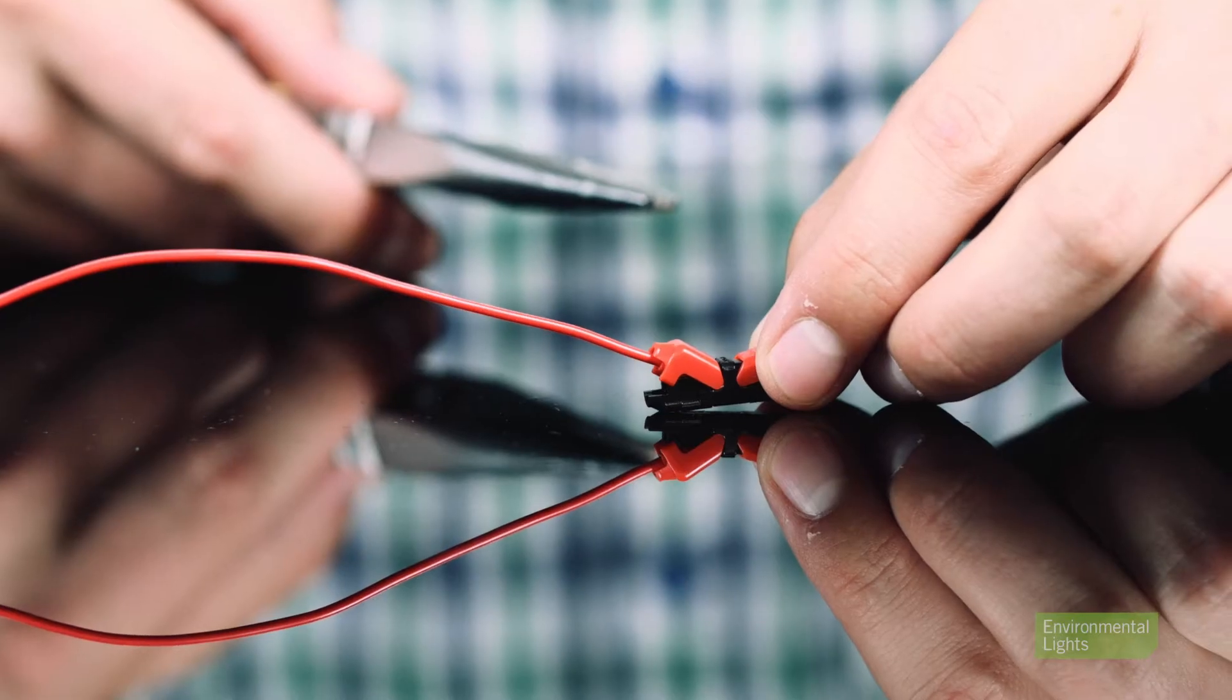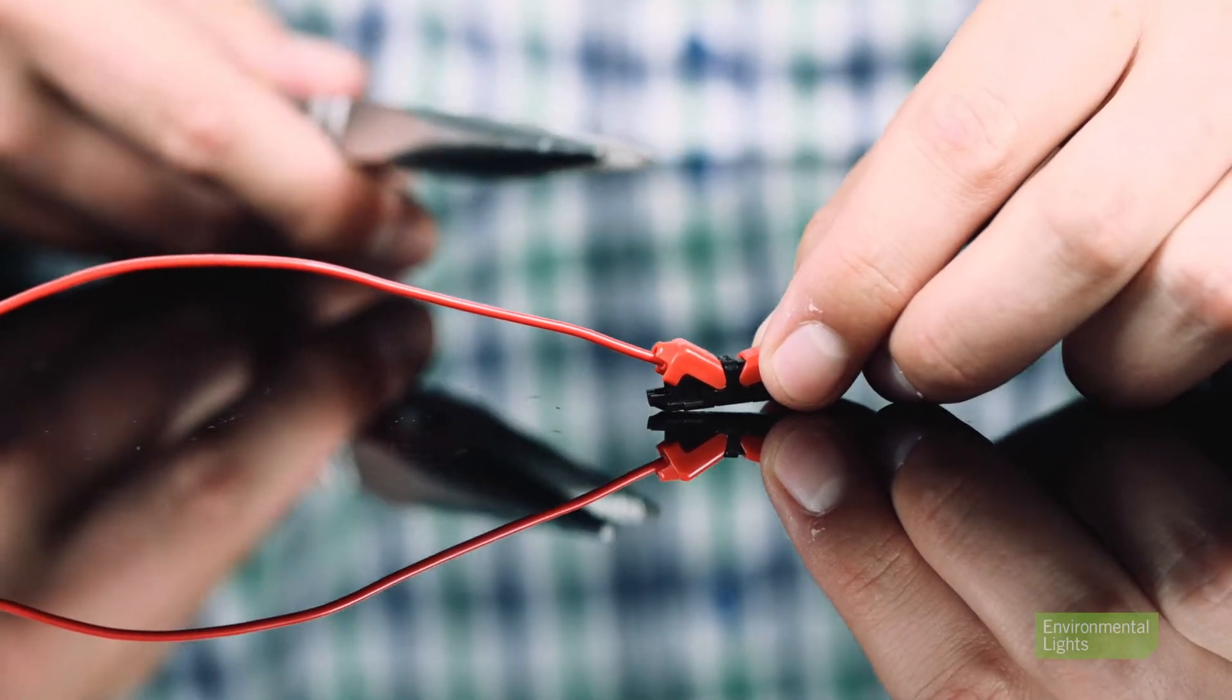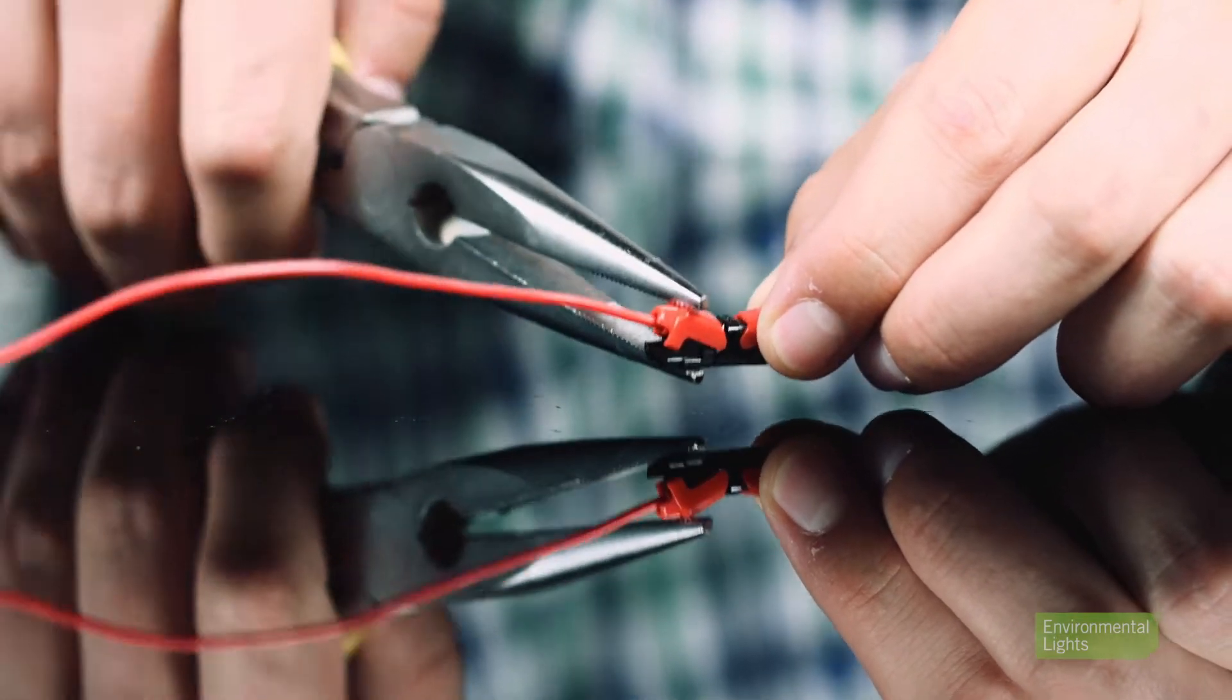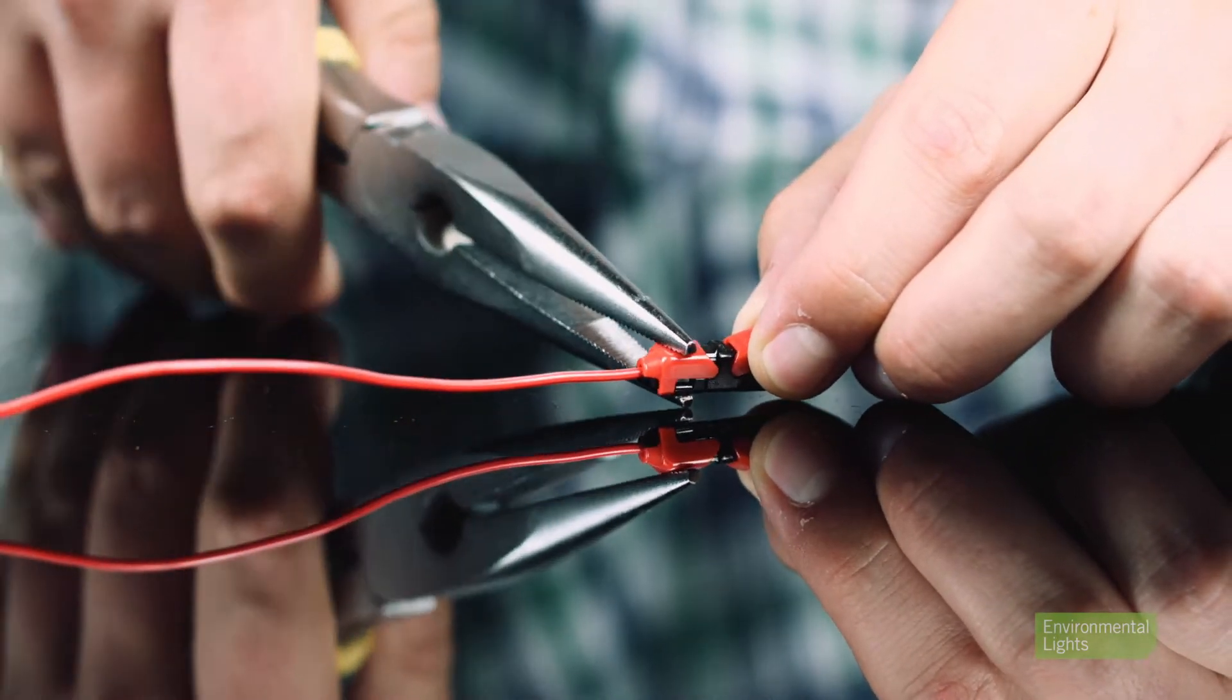The force of closing the connector will cause the v-shaped internal contacts to slice into a wire jacket, securing the wire and making contact with the wire strands.